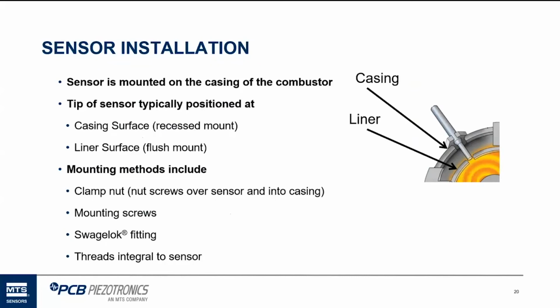This is four different methods that they use for mounting. We have sensors that mount in all these different ways. The clamp nut, which is probably my favorite mounting method, is just a nut that moves back over the top of the sensor and screws into the casing of the combustor. There's mounting screws. It's the sensor that would mount up on top of the casing, and there's some screws that hold it on. There's a Swagelok style sensor, and that's typically used on retrofits. It's not used by OEMs on new builds. And there's also threads integral to the sensor, which is my least favorite way to mount these sensors, because if you've got a big hardline cable attached to the sensor and you're trying to screw it into the combustor, it's kind of painstaking.